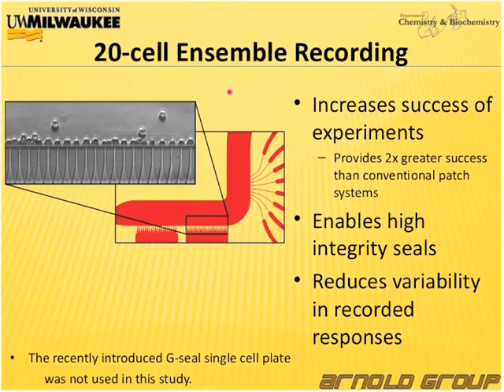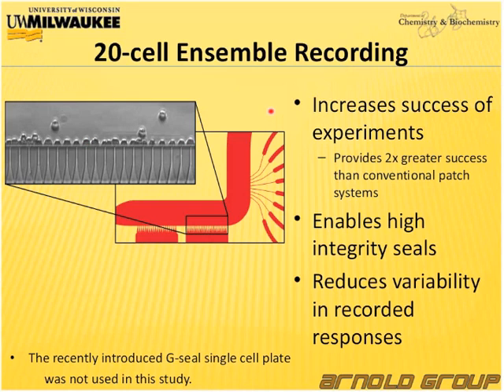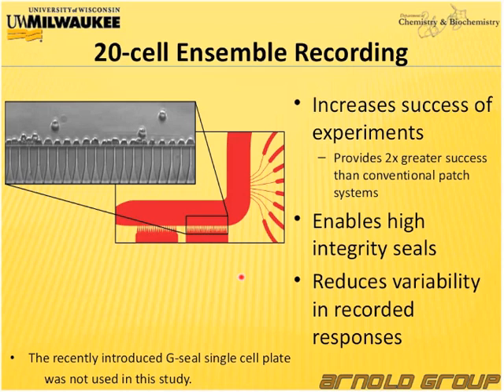The trapping zone was very important for us because the IonFlux instrument is one of the few instruments that can actually trap multiple cells — 20 cells to be precise, as shown in the picture here. All 20 cells are individually patched by one trapping zone, and we have two trapping zones per ensemble. So we are actually patching 40 cells for each ensemble, which gives us a very high success rate and enables high data integrity with very minimal variability.